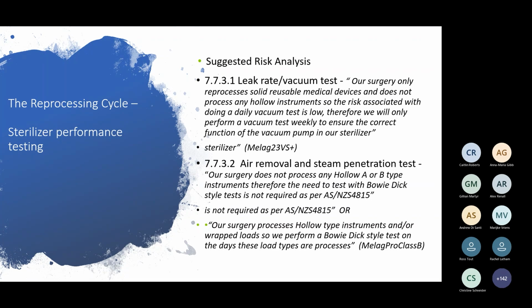Air removal and steam penetration. Our surgery does not process any hollow A or B type instruments. Therefore, the need to test with Bowie-Dick style tests is not required as per Australian Standard 4815. Or, our surgery processes hollow type instruments and or wrapped loads, so we perform a Bowie-Dick test on the days these loads are processed. So that's if you have like a MELAG Pro Class B. So if you do B loads, then that could be your risk assessment that you do for your machine.